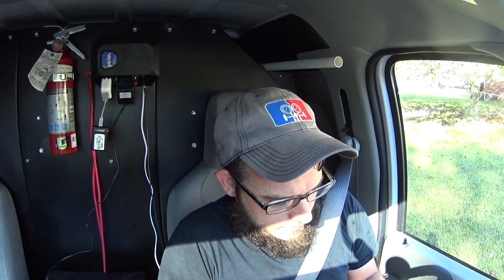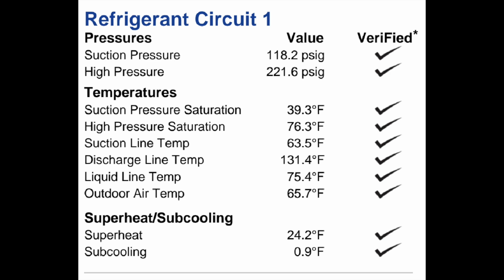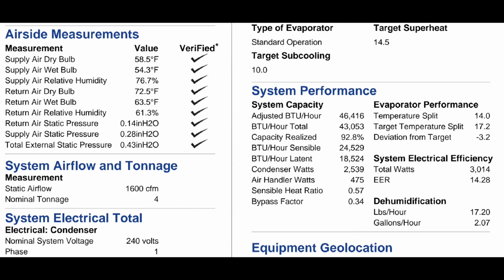So the system was a little off on the subcooling, but all in all it was performing at 14 EER, which is a positive thing.